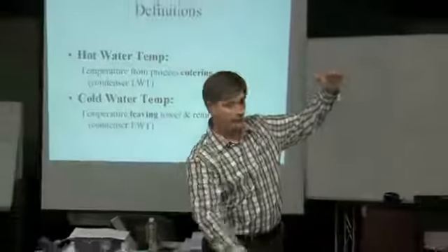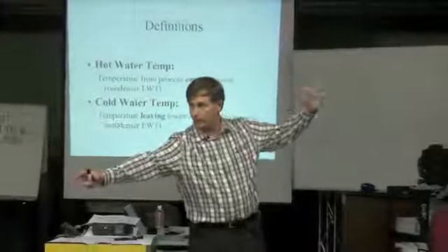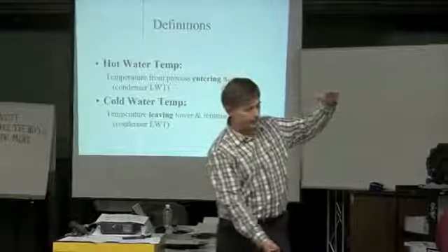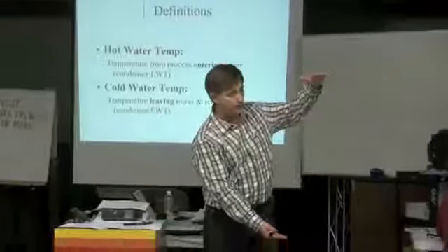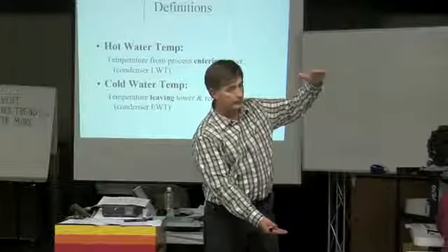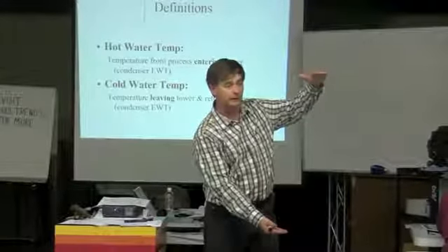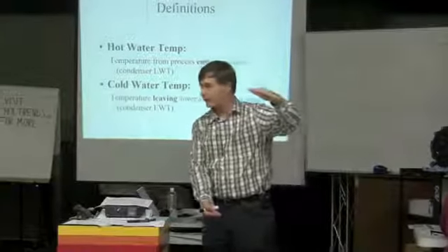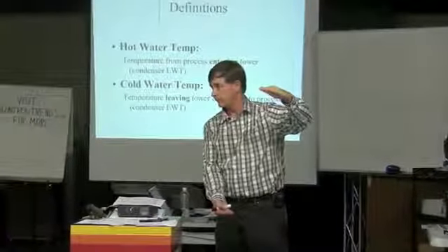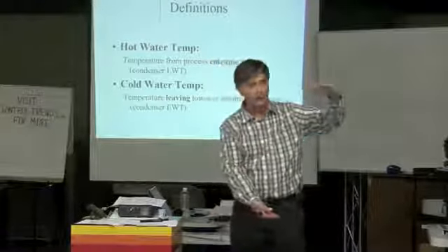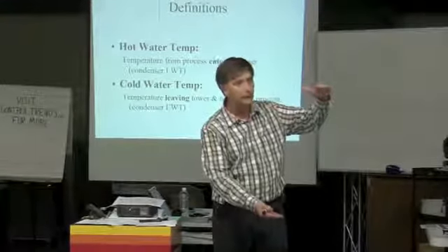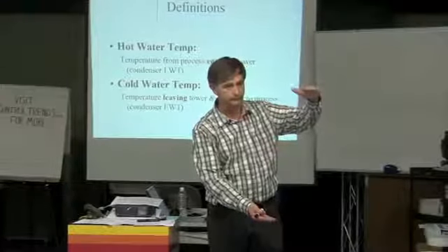So if you're taking water out of one cell and putting it in both cells, but you've got to equalize, you've got about this much water pressure. How much is that in PSI? Well, you're looking at about 1 PSI difference, because 2.3 feet of water column equals 1 PSIG.